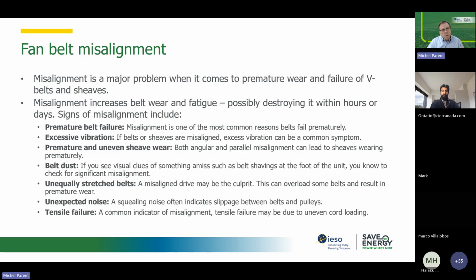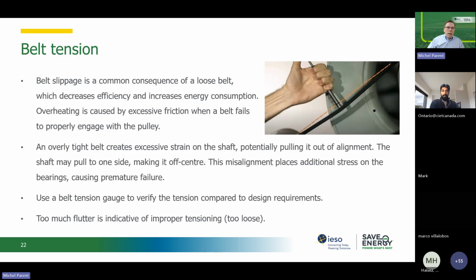And again, we have in the slide the main point that will allow you to say, or your operators should be aware of that. Why do I have belt misalignment? It's because of those possible causes. If you see premature belt failure, belt dust, if they're not equally stretched, that would be misalignment. Hopefully you do have a tool to verify the tension. That should be part of your annual PM program, especially for the larger system.